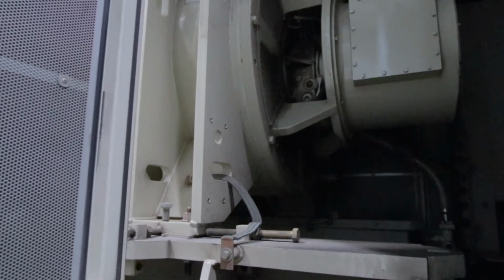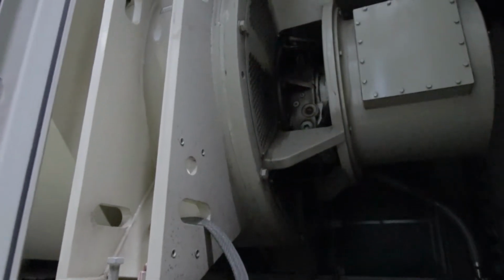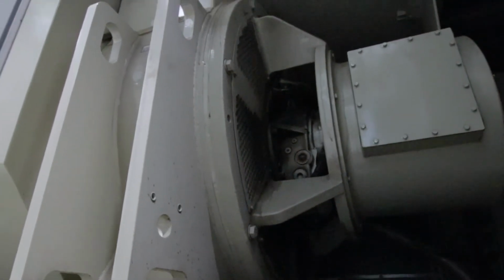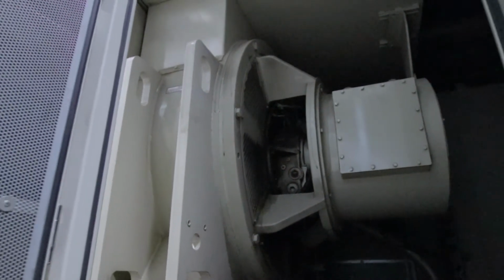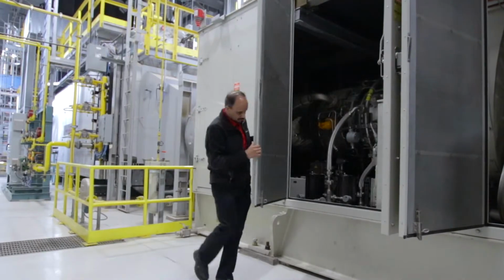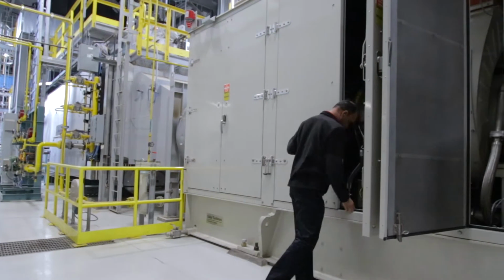That's also very important. This gas turbine has been running for 3 years now. It has about 22,000 operating hours on it. It is being serviced under a full comprehensive long-term service agreement with Solar Turbines. That is still in effect, and the accrual for an overhaul at year 4 or year 5 has been made year after year, and so the system has been well maintained.